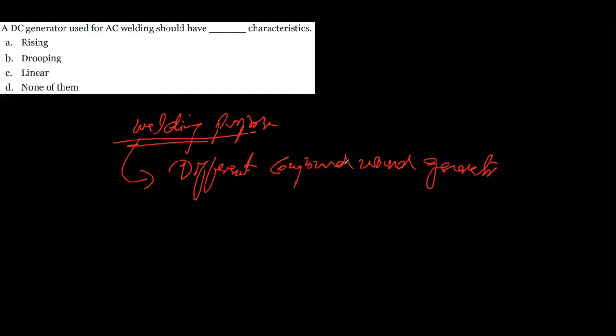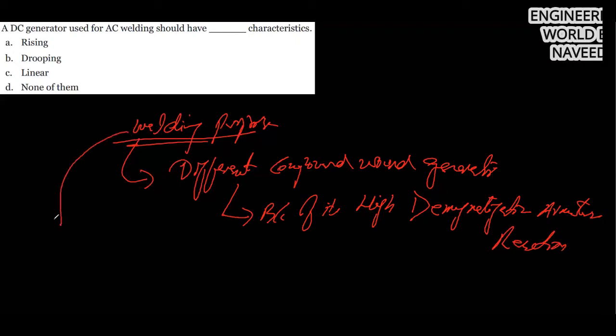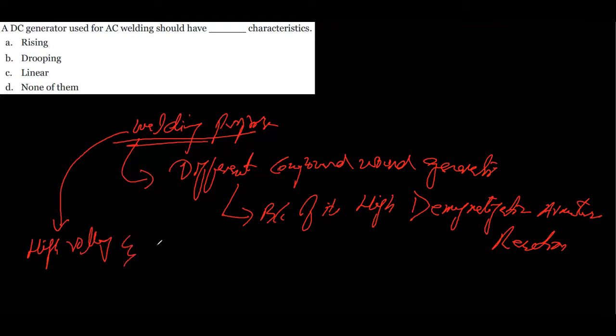We use a differential compound DC generator for welding because of its high demagnetizing armature reaction. For welding, the demand is high voltage drop and constant current, and that is fulfilled by the differential compound DC generator. So a DC generator used for welding should have a drooping characteristic.